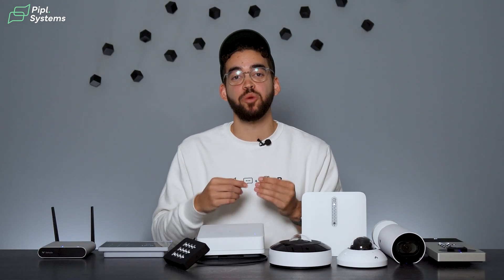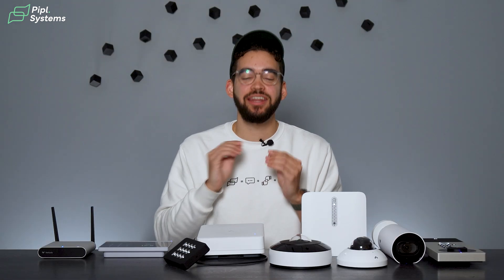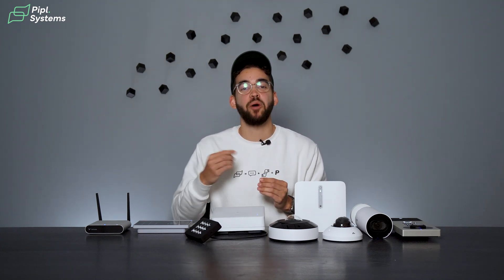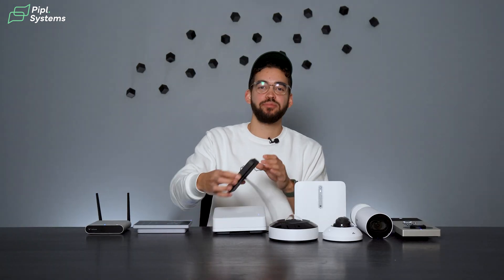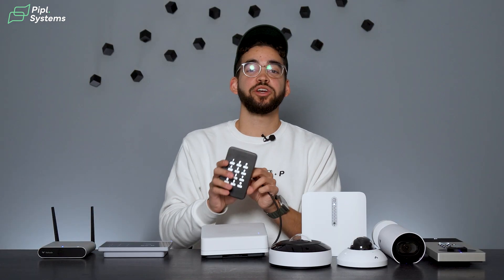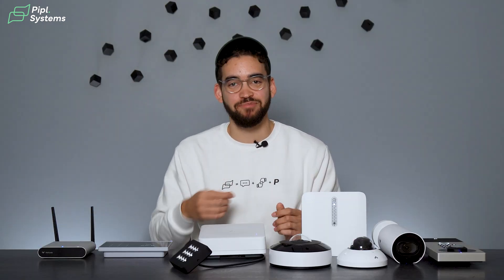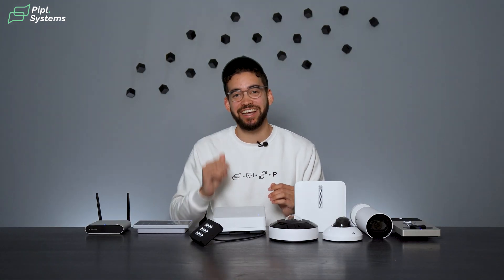The AC12 can power most electronic locks and REX devices, and supports native in-and-out badging with any combination of Verkada or third-party readers. It also includes PoE passthrough to provide consistent data and power to PoE+ peripheral devices such as Verkada cameras. Right now it's powering the AD64, Verkada's door reader with keypad. If a project has more doors than one controller can handle, you can daisy chain them for larger facilities. It's also worth mentioning that their access control supports wireless locks from both ASSA ABLOY and Allegion.